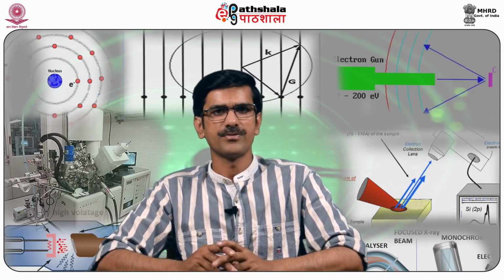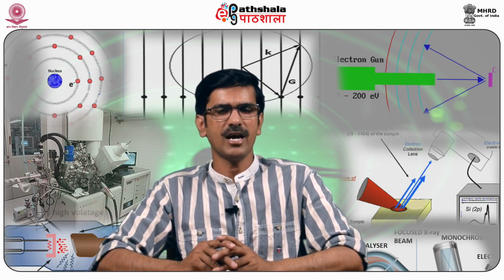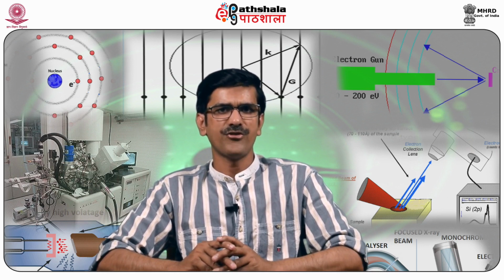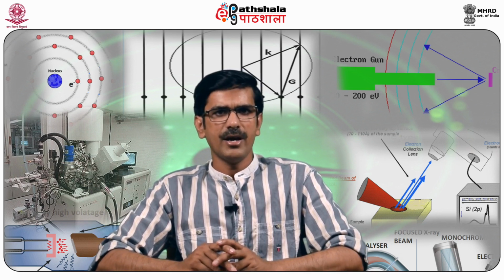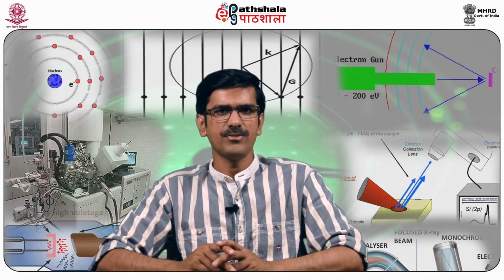Now the gases. One of the main problems in studying the gases is that a high pressure is desirable in the region of ionization in order to obtain reasonable signal strength. At the same time, the pressure should be sufficiently low so that the electron does not suffer a collision, particularly an inelastic one, between the time it is ejected from the atom or molecule until it strikes the detector.